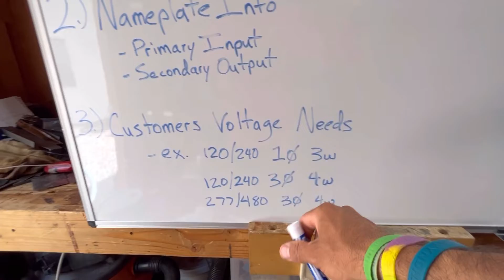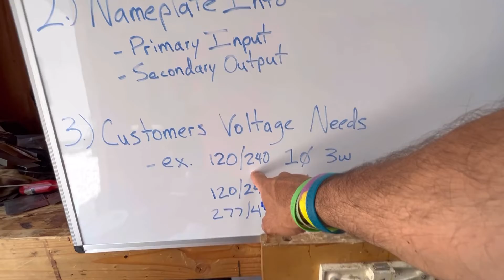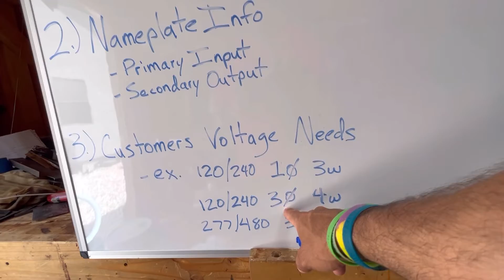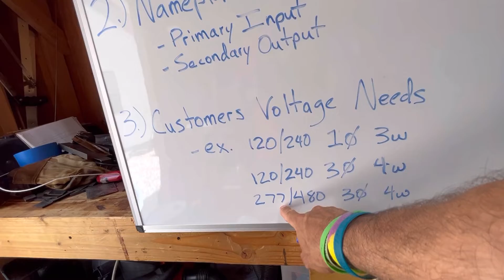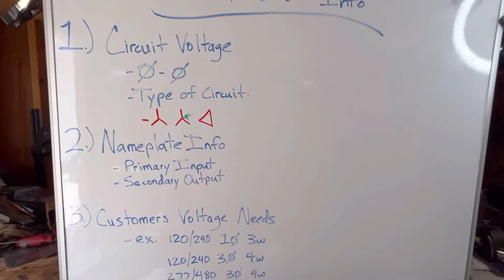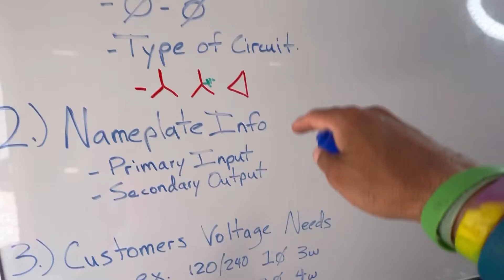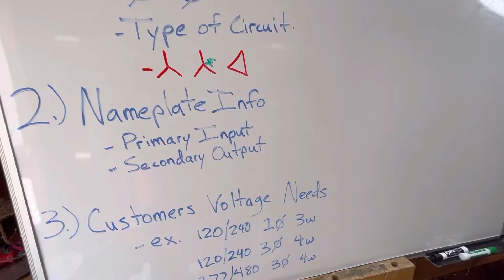And finally, the customer voltage needs. So there's different ways they can tell you this information. For example, here we've got 120/240, single phase, 3-wire, 120/240, 3-phase, 4-wire, 4 wires meaning 3 phases and a neutral, and 277/480, 3-phase, 4-wire. So what we're going to do now, guys, is we're going to break down each one of these categories, determine how we get that information, what it means, and how to determine the hookup. It's actually pretty dang easy. Stick with me.